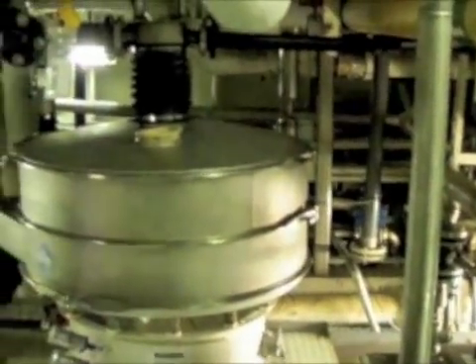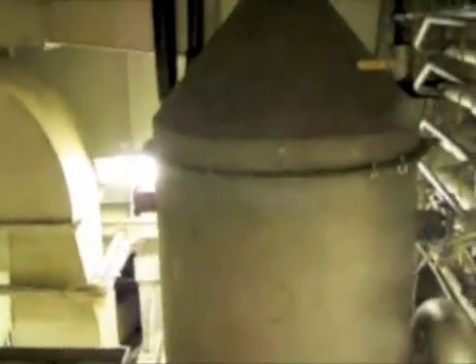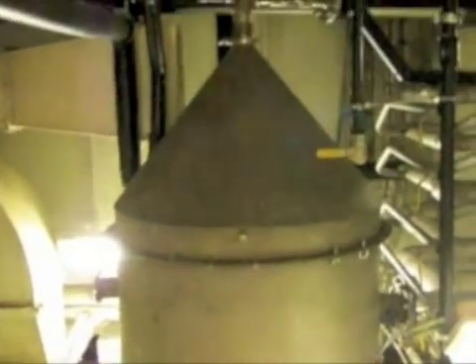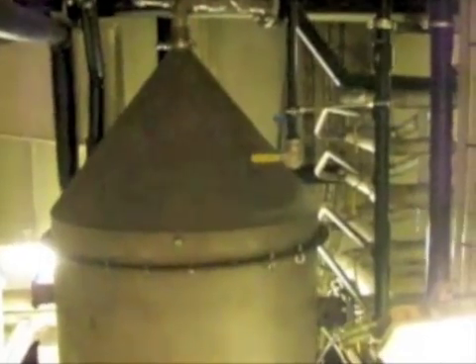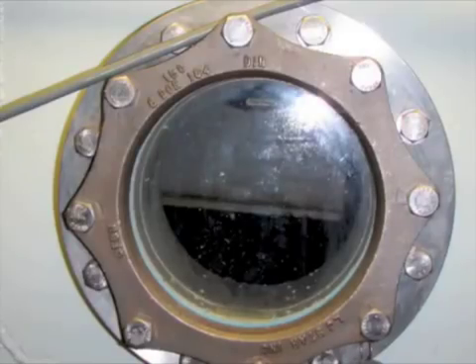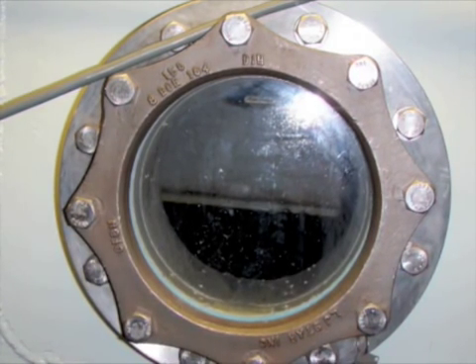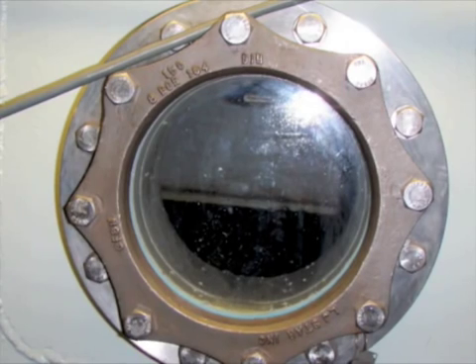Waste from the shaker screens falls by gravity into the sludge reduction tank. Here it's treated with ozone, passed on to the residual holding tank, and landed ashore. Water from the aft galley tanks passes through the grease separator module and into the Blackwater storage tank and onto the AET. This water in the AET is now pumped into the hydraulic separator system.